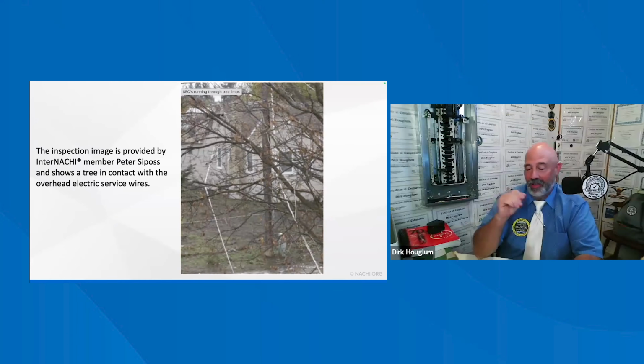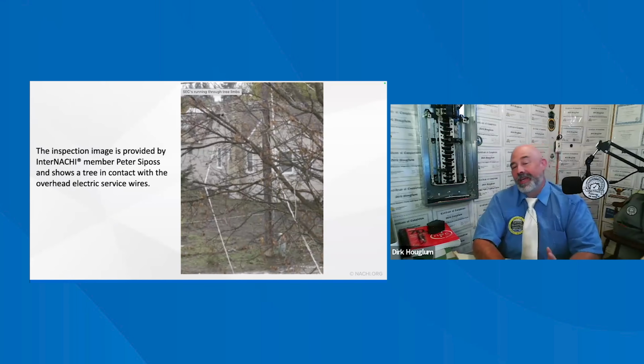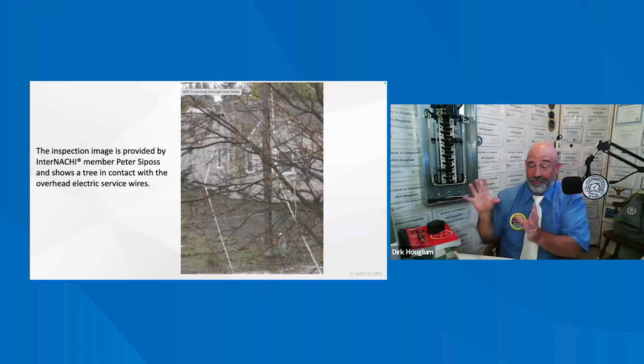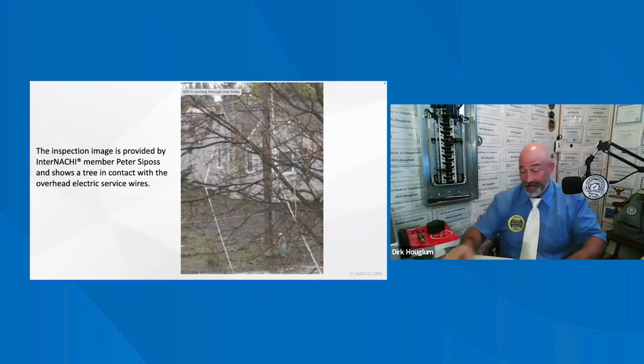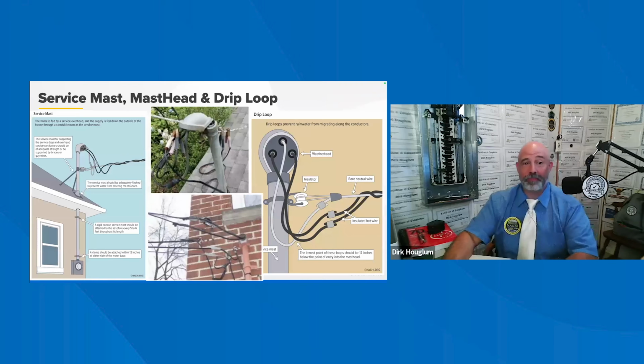I saw one where the wires actually grew inside the tree, so it was there for quite a while. Also remember that the branches are heavier during the summer and can weigh down on the conductors. What may be marginal during the winter months may cause some problems later in the growing season. The inspector should recommend that any leaves within that 5 to 6 foot around that cable should be really cut back. So that is no joke.